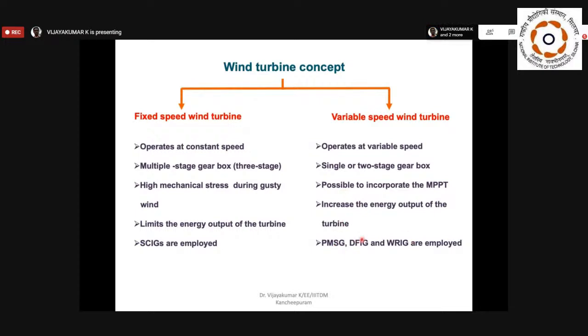These are the generators normally employed in variable speed wind turbines: permanent magnet synchronous generators, DFIG (doubly-fed induction generators), and WRIG machines. Here, apart from the permanent magnet machine, the DFIG and WRIG normally use slip ring induction machines. You have studied in electrical machines that there are two types of induction machines: the squirrel cage machine and the slip ring machine. So these two topologies, DFIG and WRIG, employ slip ring machines as the generator.